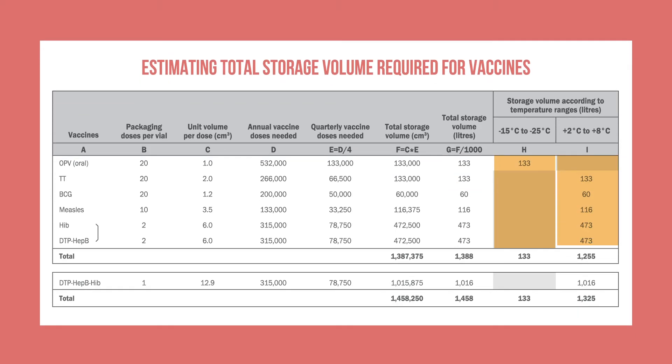Copy the total volume for each vaccine and diluent to the appropriate temperature range. With the exception of OPV, all the vaccines in this list should be stored between 2 and 8 degrees Celsius. Finally, add the volumes together to get the total storage volume required for each temperature range. This will help you determine your needs for different types of storage such as vaccine refrigerators and freezers. In this example, the quarterly delivery of vaccines will require at least 133 liters of freezing capacity and 1,325 liters of refrigeration capacity.